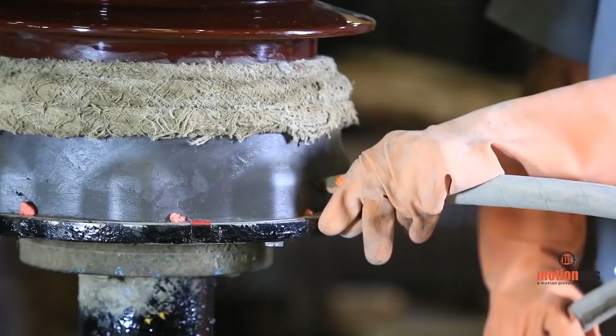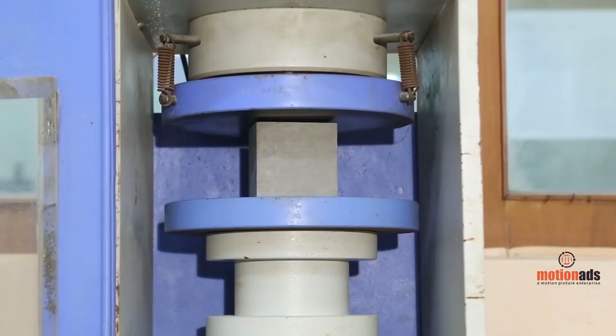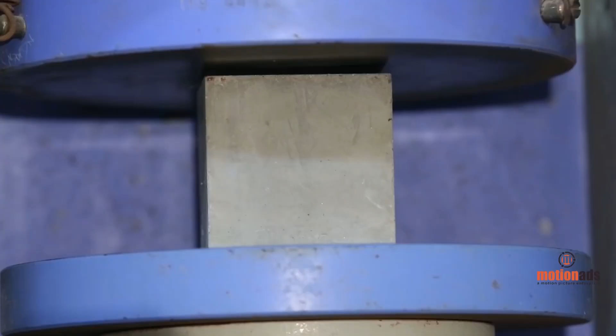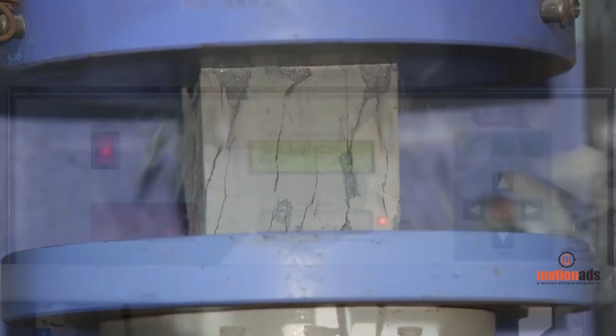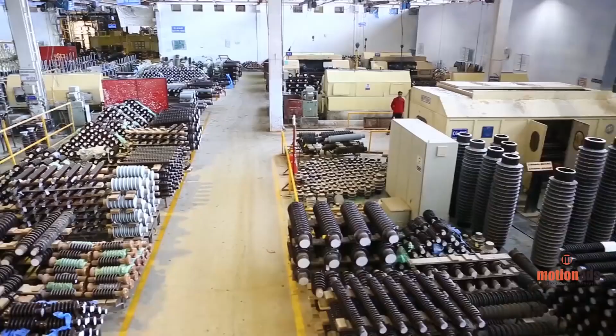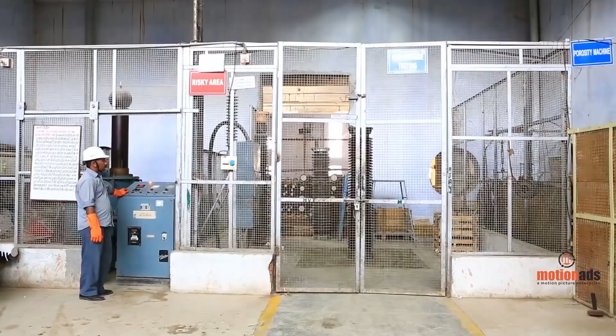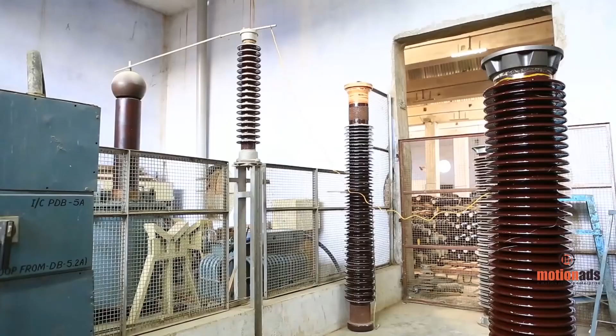The assembly is done by high-pressure injection method. The cement used is of special type, collected from approved suppliers, duly tested for mechanical and other properties and stored properly. Finally, each and every insulator undergoes routine plus special mechanical and electrical tests to comply with customer specifications.